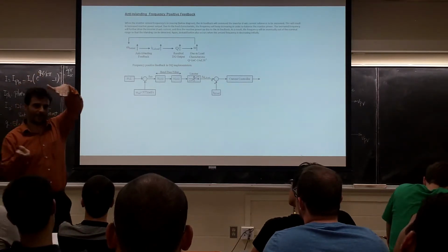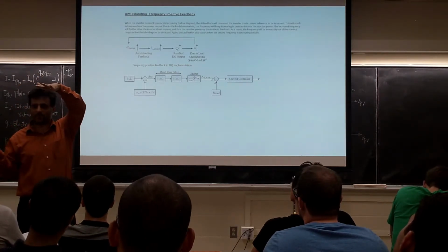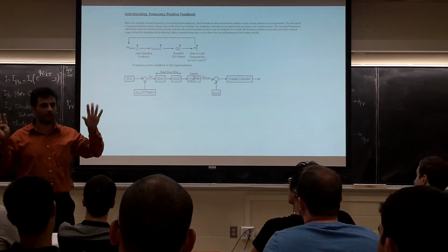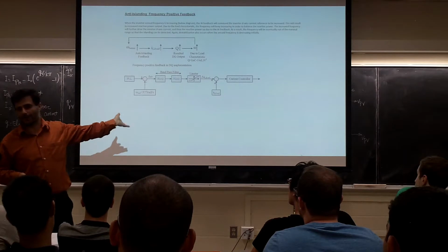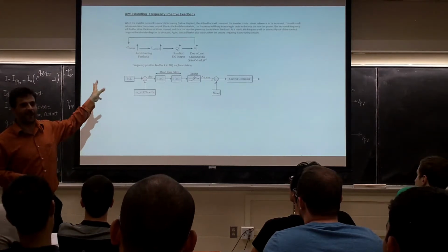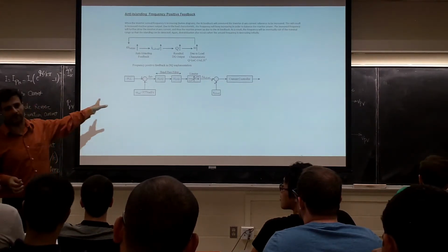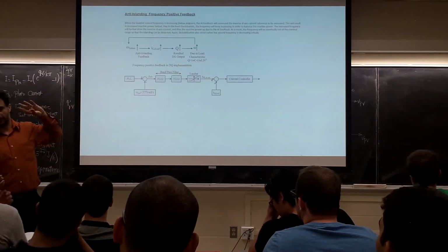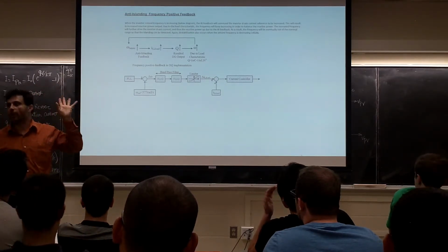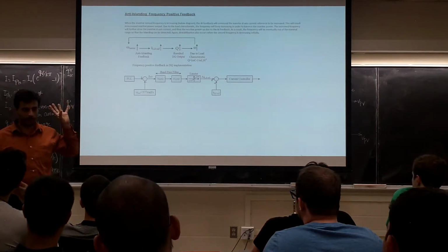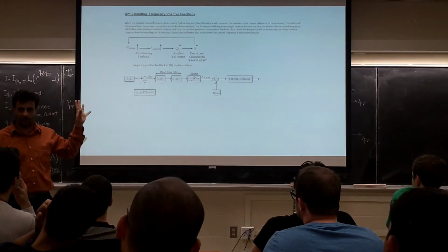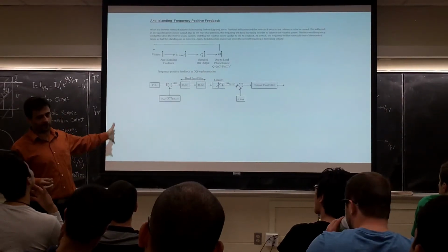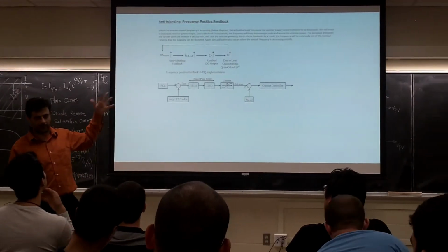And you have a limit. As soon as you pass, for example, 0.8 hertz from the origin, if something is wrong, shut down. They call it anti-islanding. If you hear about anti-islanding, it's an algorithm. There are lots of control algorithms in inverter controls. Basically, this one recognizes whether the grid is there or not. That's very important to know, that the inverter should be smart. This is a smart inverter, with all these kinds of algorithms built inside.